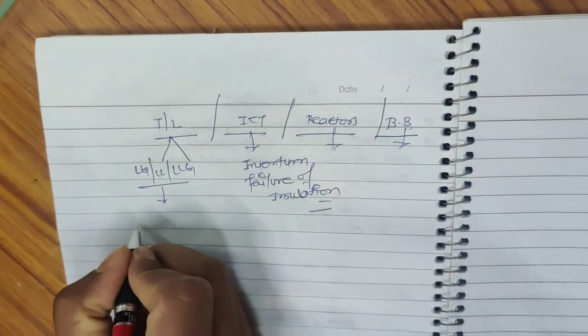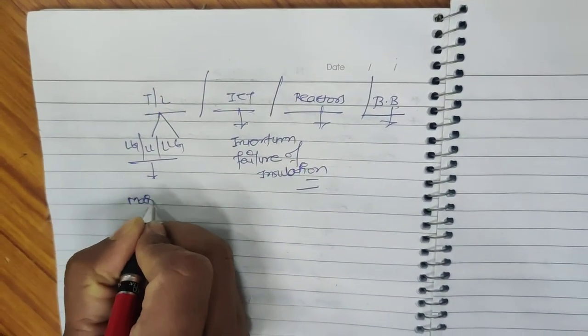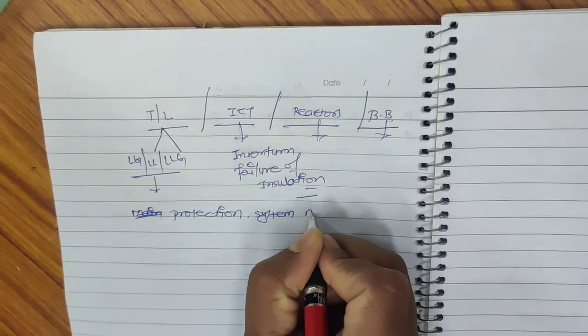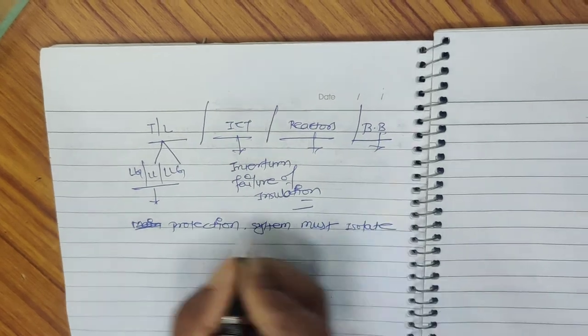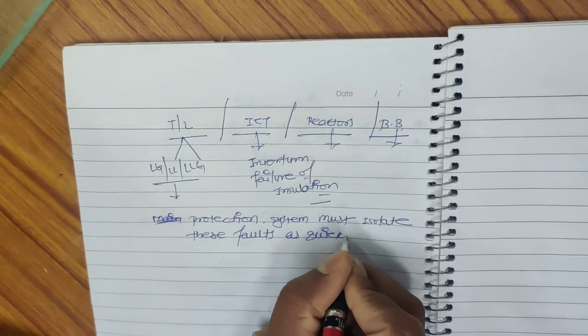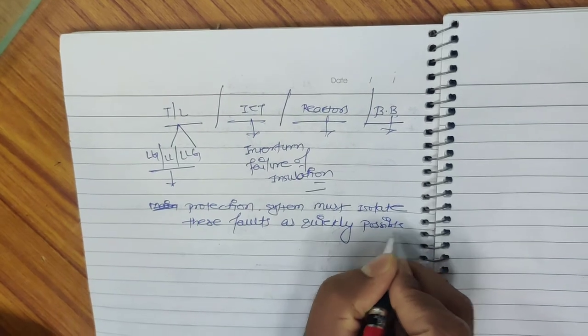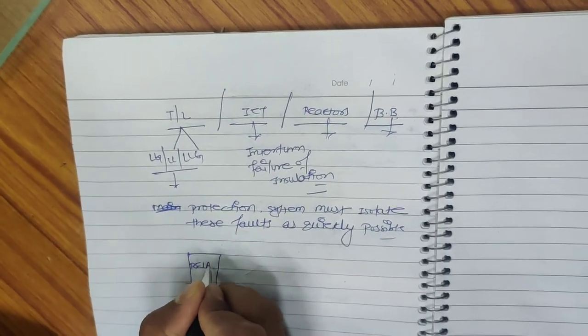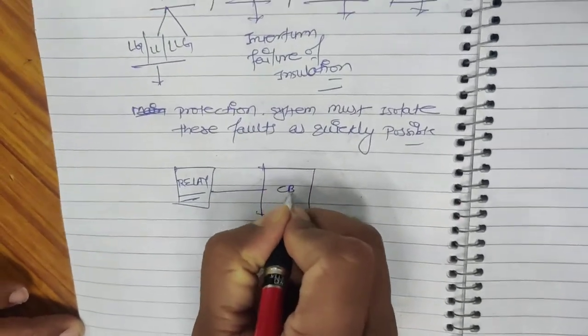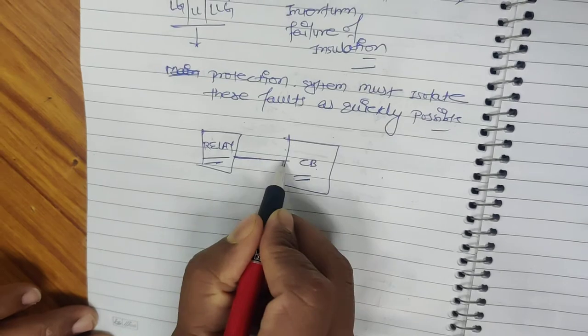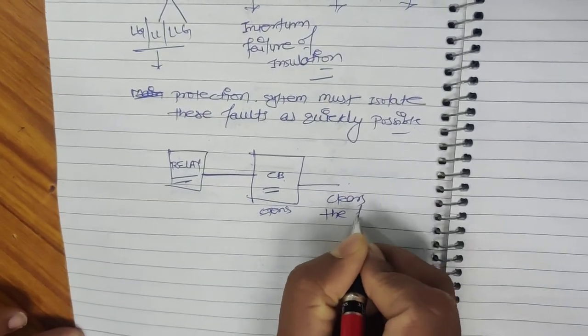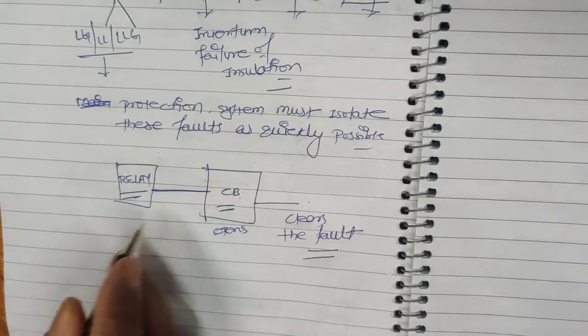We cannot overrule the chances of fault. But the main purpose of the protection system is to isolate this fault as quickly as possible. To isolate the fault quickly, the first thing we need is a protective relay. The protective relay, after detecting the fault, sends signals to the circuit breaker. The circuit breaker, after receiving this signal, opens and clears the fault. This is the basic philosophy inside every protective scheme.